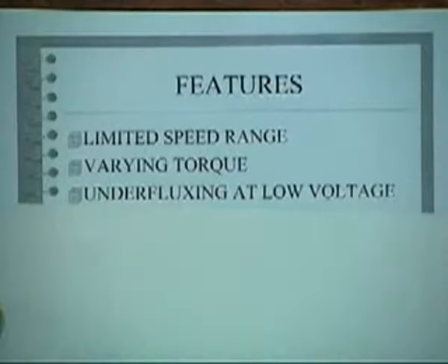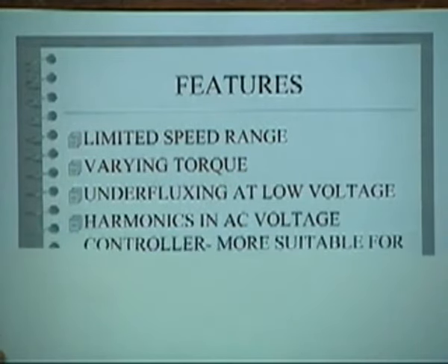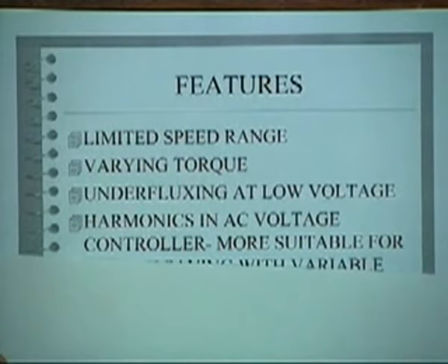Then another factor is there is underfluxing at low voltage. So you are not operating at nominal flux. If you reduce the voltage, operating flux is small. There is underfluxing. Okay. Then if you use an AC voltage controller, then there are harmonics in currents and voltages. If you have a power electronic controller, back-to-back thyristors, that is one of the problems that you will have. So you have to reckon with harmonics in the supply current.